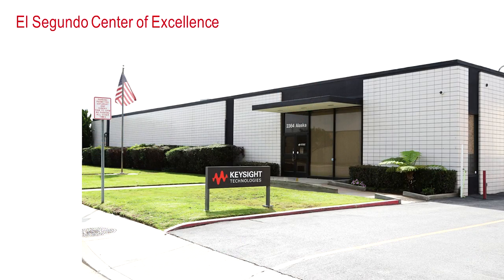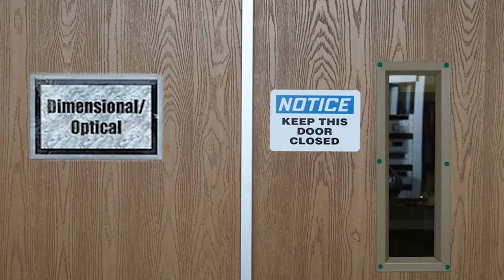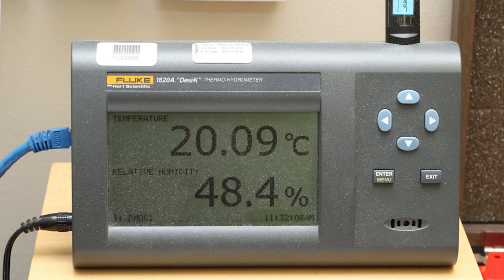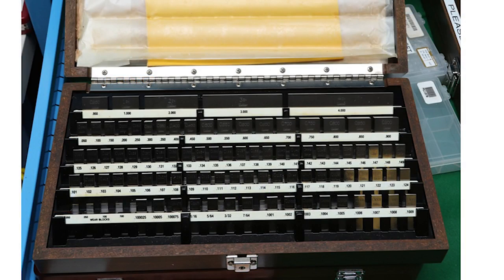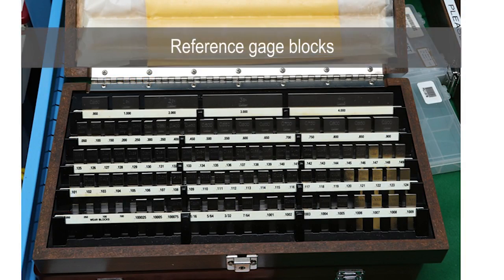Today I'd like to talk to you about what we're able to do in standards lab calibrations at our El Segundo Center of Excellence. First thing you see is a locked door. What it means is that we understand that temperature stability is very important. When you go inside, you're going to see a thermometer with the current reference value. In order for these measurements to be valid, it has to be at 20 degrees Celsius plus or minus a half a degree.